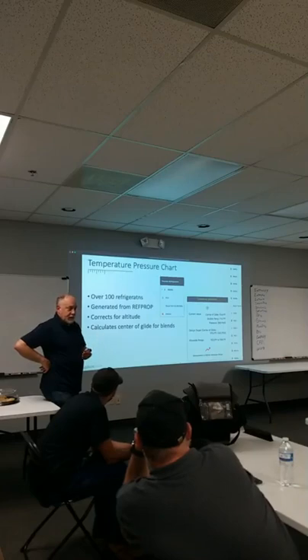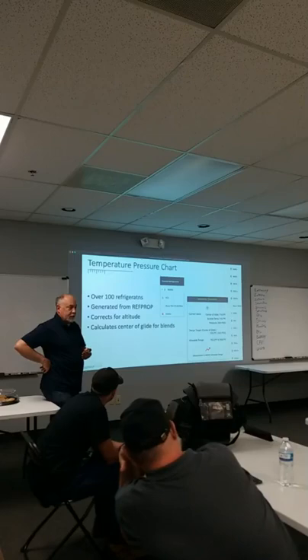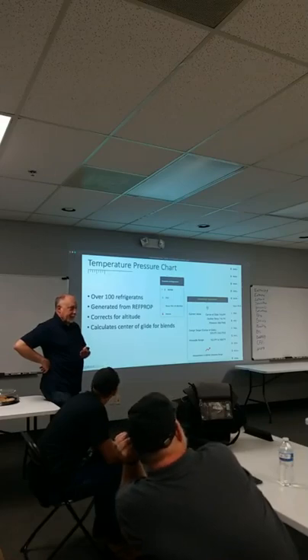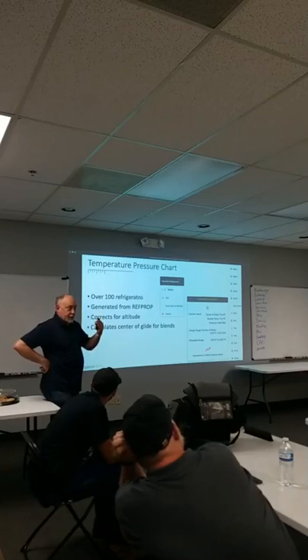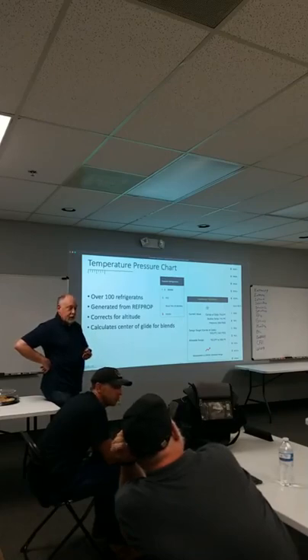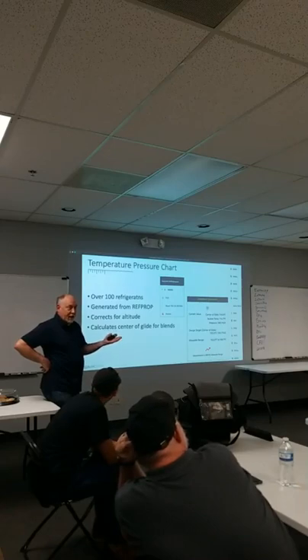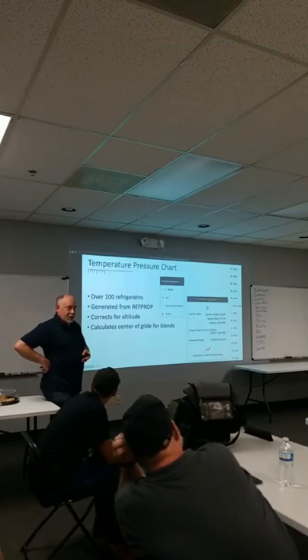Anybody ever work at altitude, in Denver or in Colorado or any high altitude? I know Phil's probably seen a high elevation temperature pressure chart, right? Because they published them when we were young boys. So you could get a pressure temperature chart for altitude. And what type of gauges do we use? Relative or absolute? Technically, our gauges are differential between there and atmosphere. When you zero out a gauge in Colorado, it's definitely not the same as a zero at sea level, right?